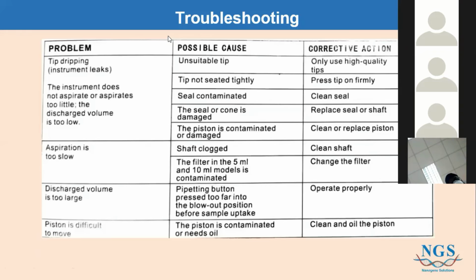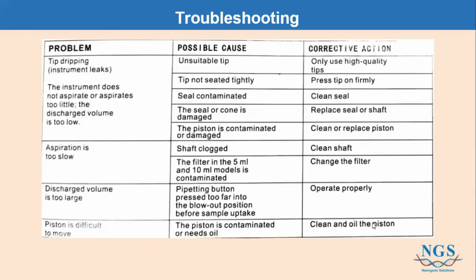Okay, so here is just some troubleshooting. You've already done your calibration, everything checks out, but when you're handling your pipette, there are still some troubles here and there. One of the most common problems that a pipette user would face is tip dripping, so liquids that don't aspirate, or there's some leakage. And I would say the most possible cause of this problem is an unsuitable tip. You always want to know what volume of pipette you're using. For example, I'm using 20 to 200 microliter, so I would need to use a 200 microliter tip. And I also need to know that the head of my tip is actually fitting into my tip cone.